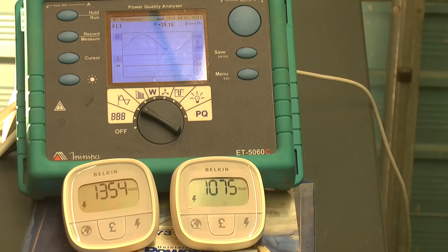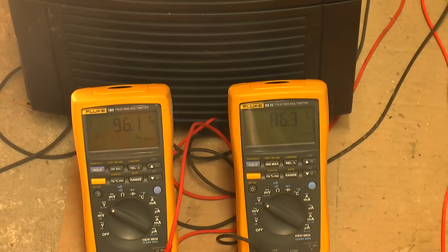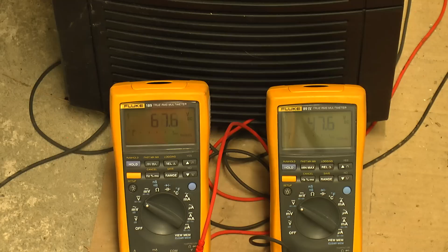Now it's realised that the batteries aren't there. And the battery voltage, the bus voltage, is creeping back down. And presumably that's a sort of safety feature because it's allowed to have a variable number of batteries fitted. That's very low for what would be two sets of 15 batteries in series, because this is for one set of batteries and this is for the other. But let me show you why.